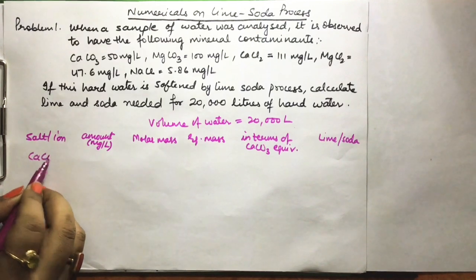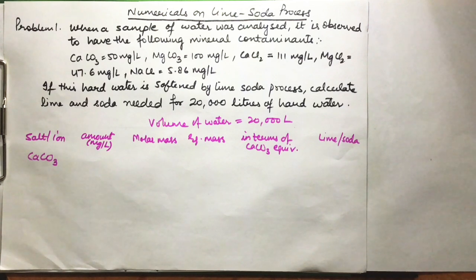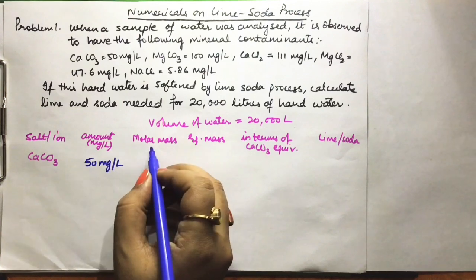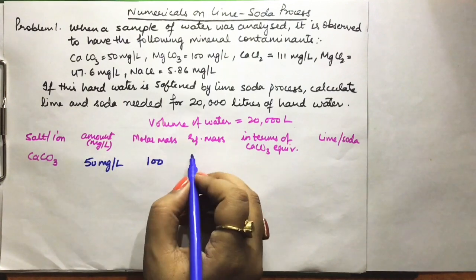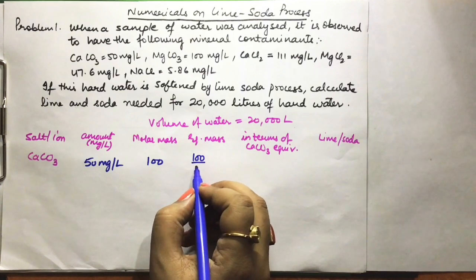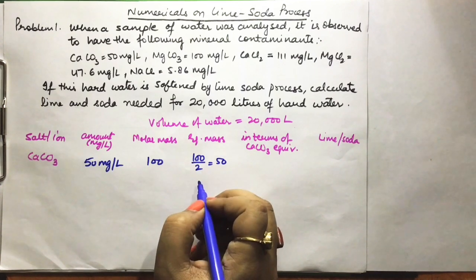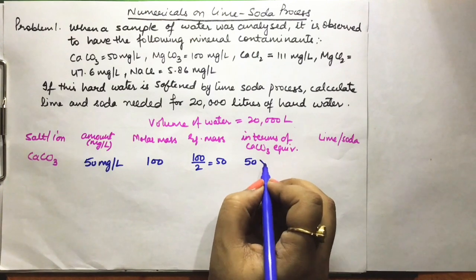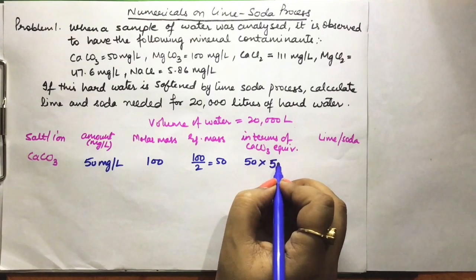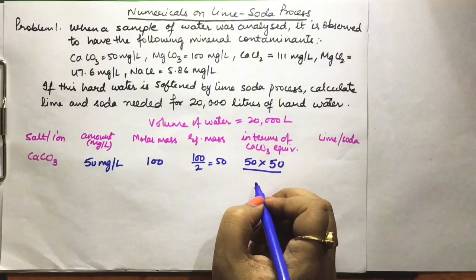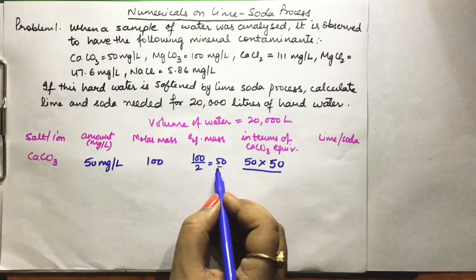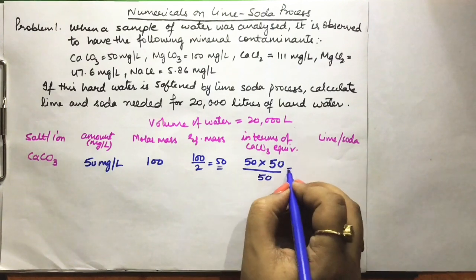First: CaCO3, amount 50 mg/L. Molar mass is 100, equivalent mass is 100/2 = 50 (valency factor 2). In terms of calcium carbonate equivalent: 50 × 50/50 = 50 mg/L. Next: MgCO3, amount 100 mg/L. Molecular mass 84, equivalent mass 84/2 = 42. Calcium carbonate equivalent: 100 × 50/42 = 119 mg/L.